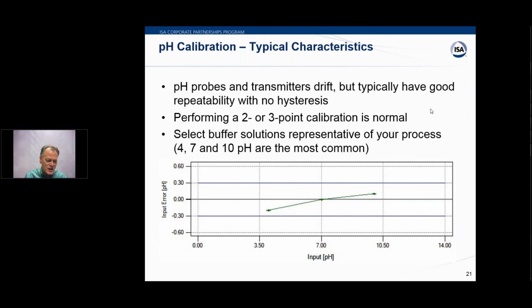And buffer solutions, I've learned, are typically better than 0.02, but as Ian alluded to, temperature can cause a pretty significant swing. So when you're doing calibration, you do need to be aware of any temperature differences in the solution versus the process.